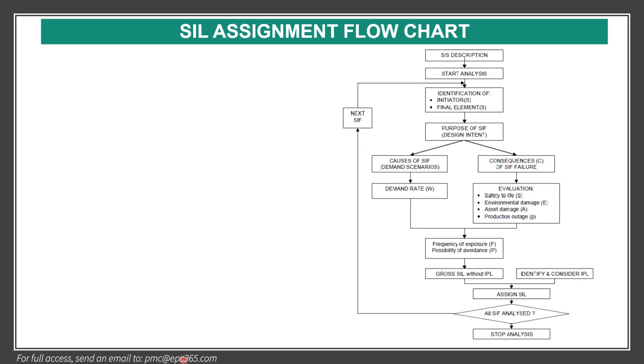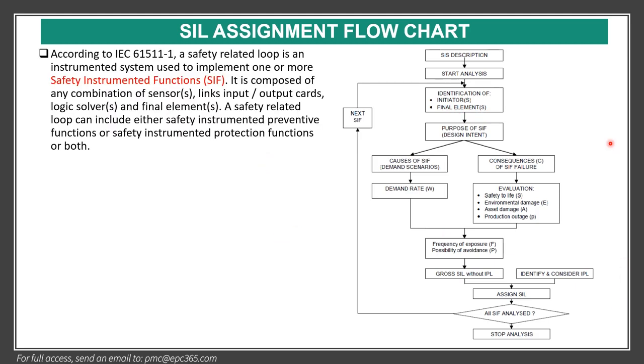Let's start by seeing the flowchart of the SIL assignment. The SIL assignment normally starts by identification of the initiation and final elements, which is according to IEC 61511. We have to identify the SIF. A SIF, or Safety Instrumented Function, is a safety-related loop — an instrumented system used to implement one or more safety instrument functions. It is composed of any combination of sensors, links, input and output cards, logic solver, and final element.